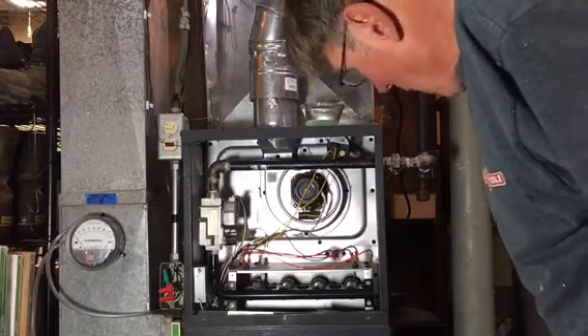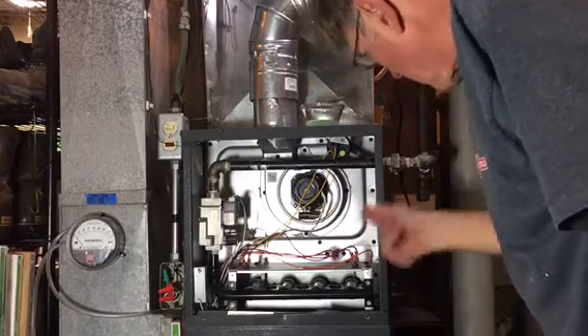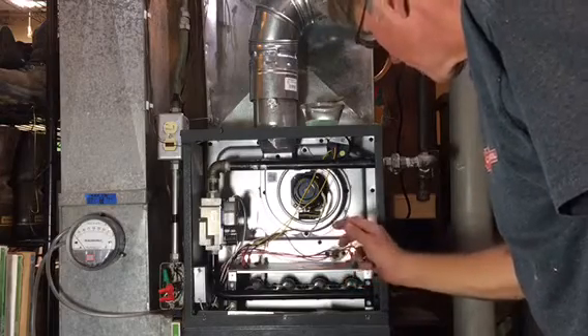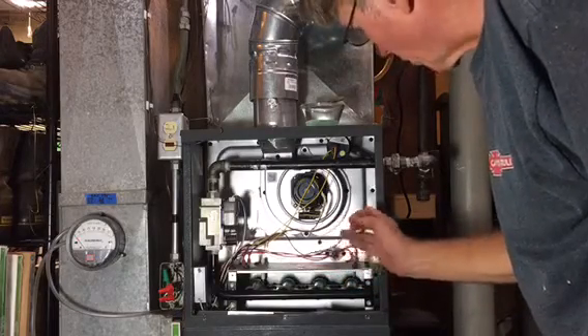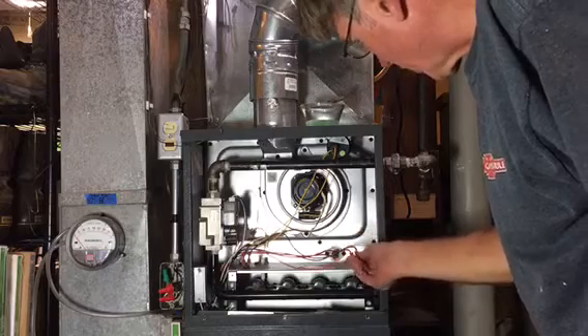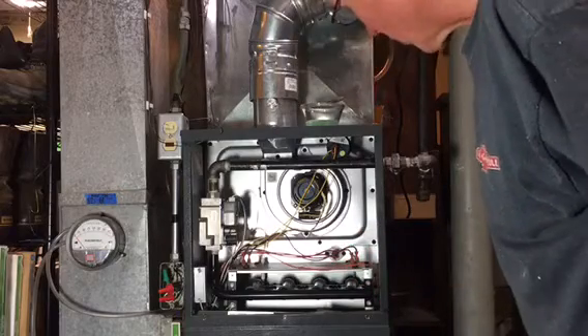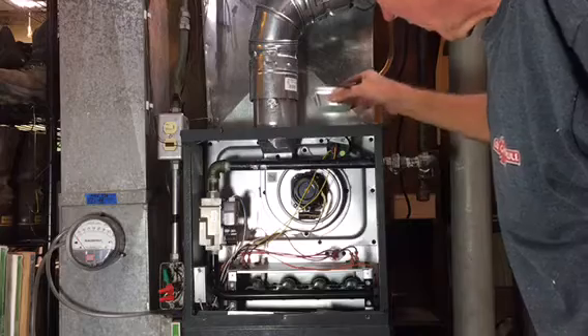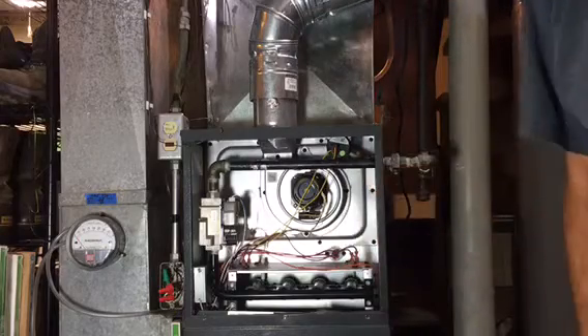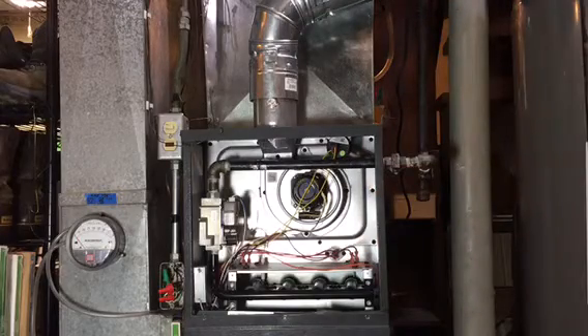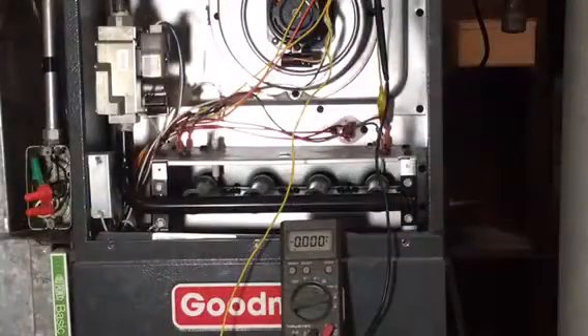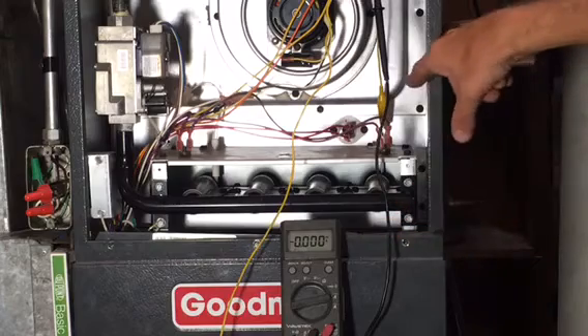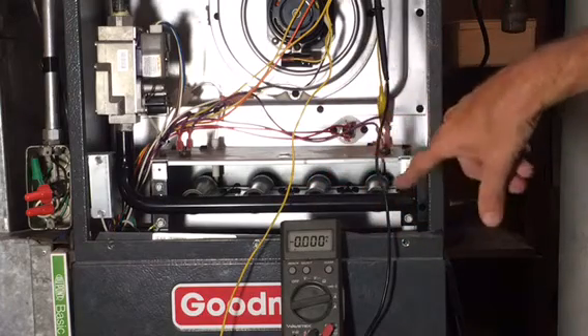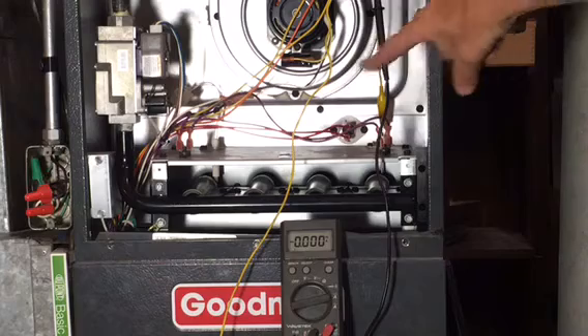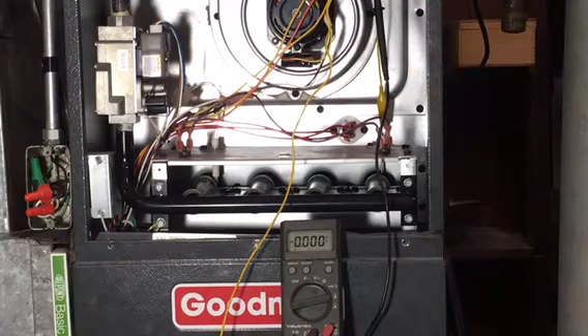We're going to power up. First, I'm going to put the meter in series between this orange wire and the flame sensor, and we'll just measure the current. It should be within a certain range. It tells us when the sensor is getting close to failure, so you can replace it prematurely instead of waiting to that cold night when your furnace won't start. Okay, we've got the DC ammeter in series with the flame sensor here, which means it just goes to the meter and then it goes to the sensor and then back to the control board.